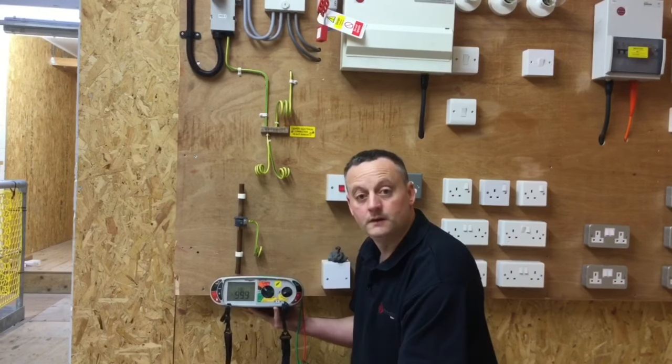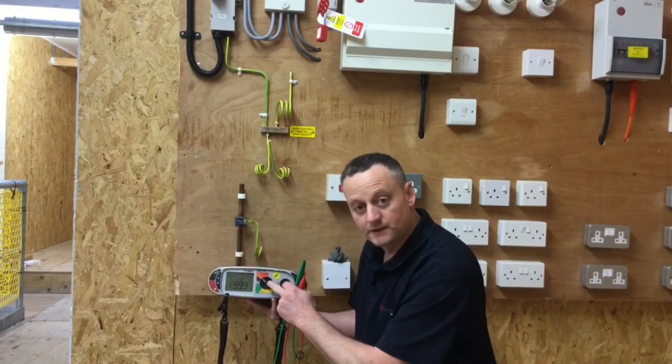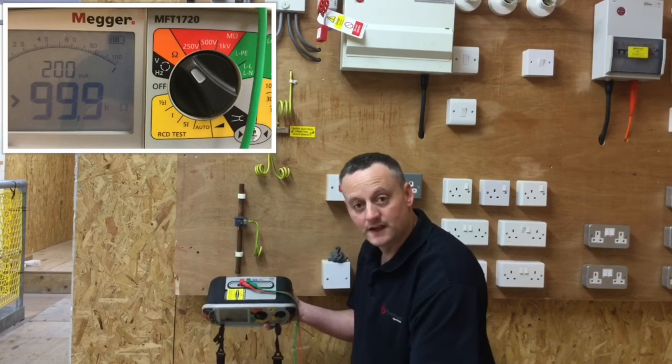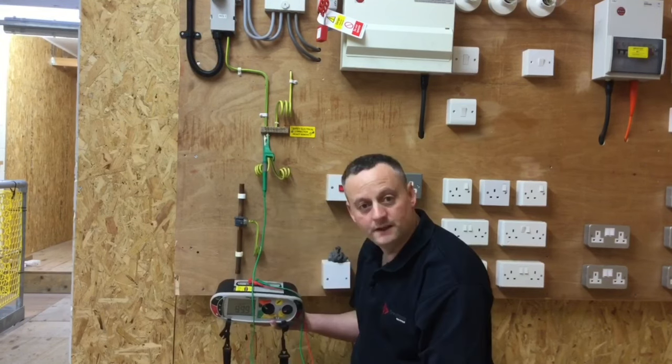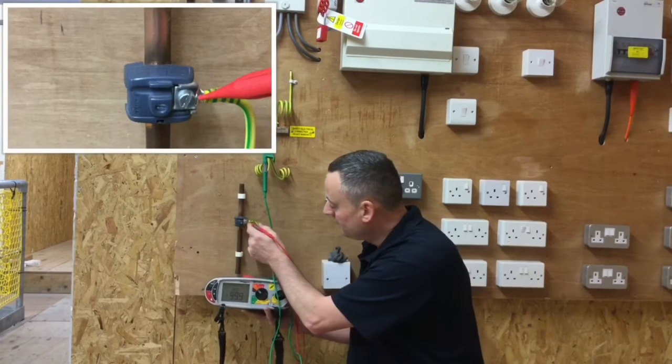We expect the reading to be less than 0.05 ohms, which is approximately 27 metres of 10 millimetre squared cable — we're simulating a domestic dwelling. If your water or gas pipe is further away than that, you'll need to increase the size to 16 millimetres squared. I've set the meter into the orange scale for measuring resistance in ohms, using the red and green leads into the top of the Megger MFT, with a crocodile clip onto the disconnected water protective bonding conductor.